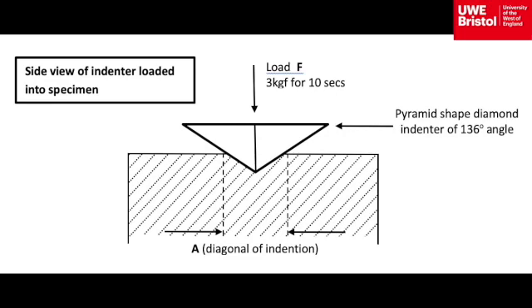Tests performed in the lab follow British and international standards. These stipulate the load in reference to the materials being tested, and these tests are at 3 kilograms force, and the duration of the time the indenter is held in place, also according to standards, is 10 seconds.